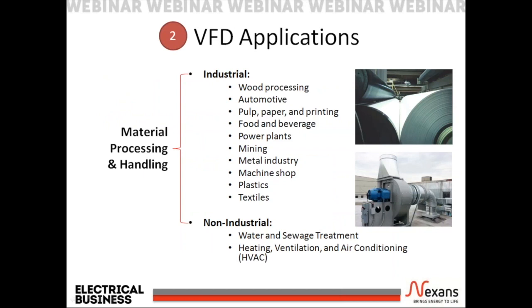VFDs are used in material handling and processing applications. These applications can be broken down into two categories: industrial applications and non-industrial applications. An example of an industrial application would be the drive motors for the paper rollers, presses, and so on for a paper mill. Even at Nexans, we use VFDs quite extensively. In our copper rod mill, as well as our wire and cable plants, VFDs are used to drive our extruders, our fans, pumps, and product conveyor systems.